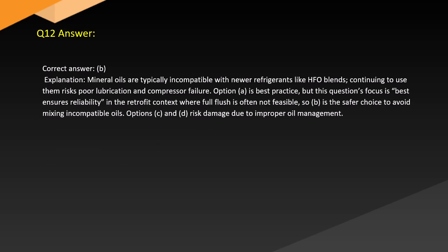Answer. Correct answer: B. Explanation. Mineral oils are typically incompatible with newer refrigerants like HFO blends. Continuing to use them risks poor lubrication and compressor failure. Option A is best practice, but this question's focus is on what best ensures reliability in the retrofit context, where a full flush is often not feasible, so B is the safer choice to avoid mixing incompatible oils. Options C and D risk damage due to improper oil management.